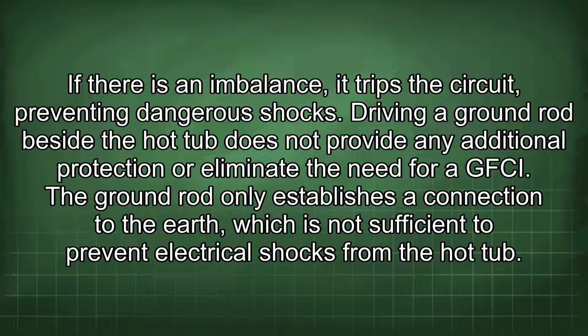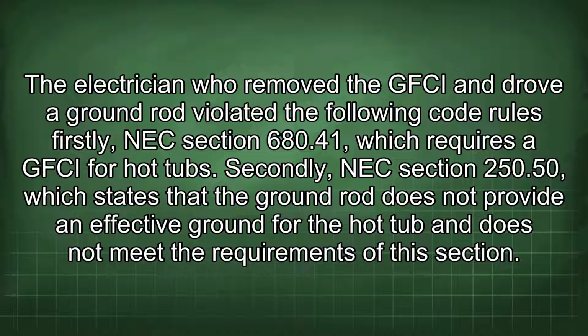Driving a ground rod beside the hot tub does not provide any additional protection or eliminate the need for a GFCI. The ground rod only establishes a connection to the earth, which is not sufficient to prevent electrical shocks from the hot tub. The electrician who removed the GFCI and drove a ground rod violated the following code rules.